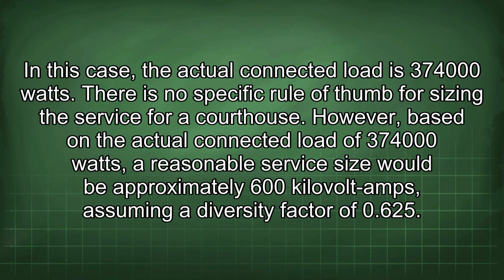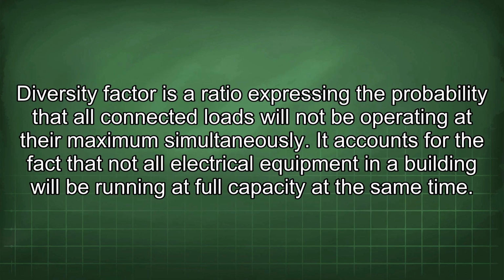However, based on the actual connected load of 374,000 watts, a reasonable service size would be approximately 600 kVA, assuming a diversity factor of 0.625. Diversity factor is a ratio expressing the probability that all connected loads will not be operating at their maximum simultaneously.